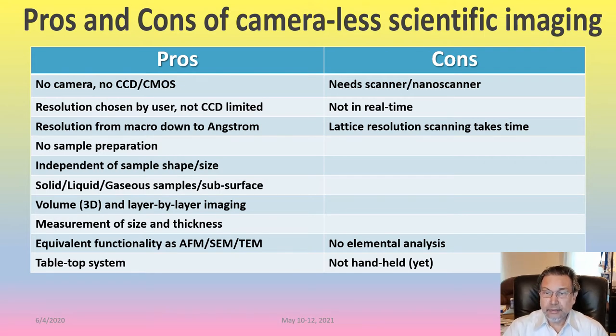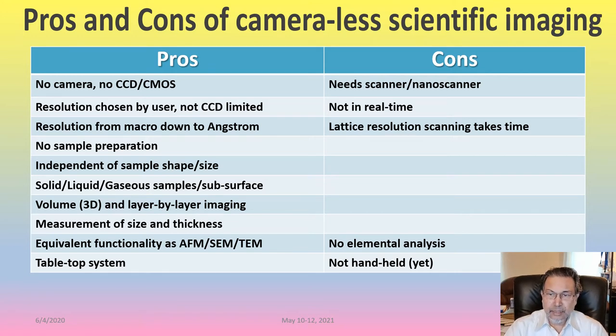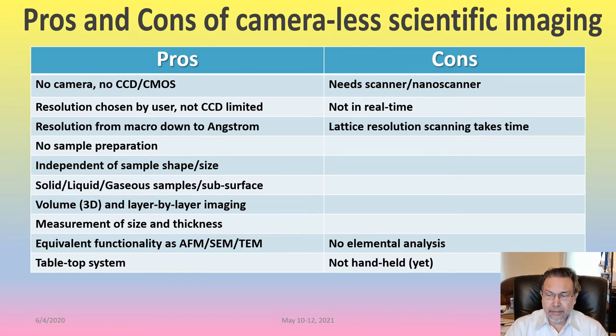The cons are that it needs a nanoscanner and it is not real time. Like a camera, you can see an image right away, but in this case we first have to digitize and then create the image. Lattice resolution scanning also takes time — a rough scan goes very fast, but if we need lattice scale resolution imaging, that fine scanning takes time.